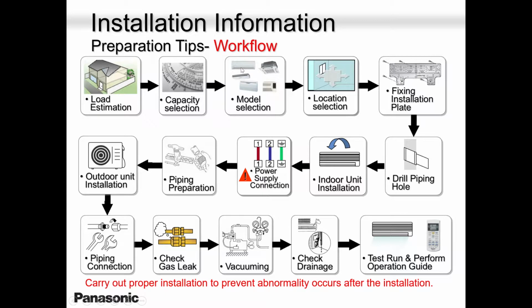So in a normal procedure, a guy will go there, do his load estimation, pick a capacity, pick a model, whether it's a wall mounted, a cassette, or a ducted, it all depends. We have all those models: wall mounted, ceiling suspended, ceiling cassette, and ducted models, okay guys? Then pick a good location, guys. Don't go close to the window. When a window gives out heat, especially in cooling, you'll get a lot of condensation. So above the window or above a door is not a good spot.